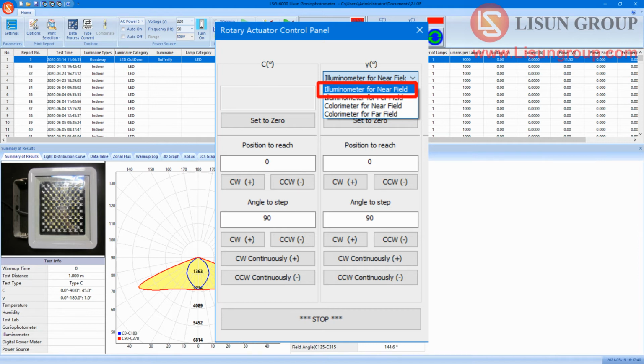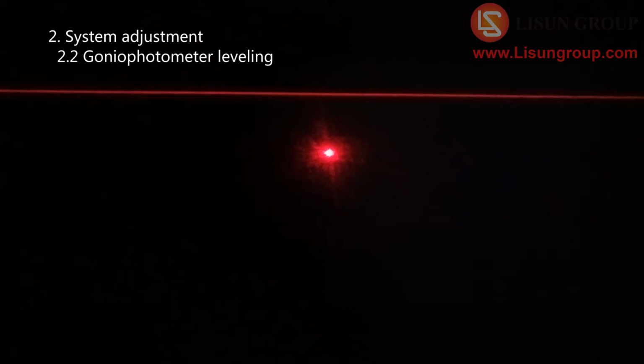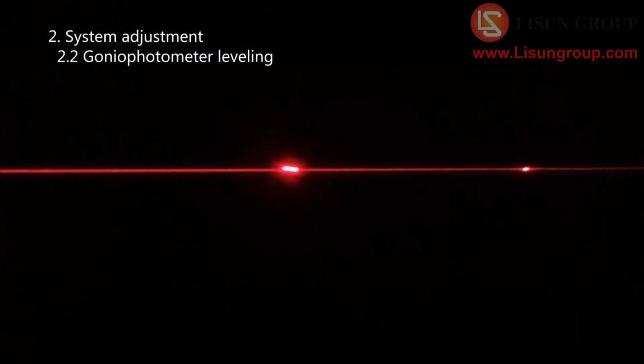Choose Illuminometer for near field. Click this button to make it rotate continuously. Then you can see the laser spot moving on the darkroom wall. Now you need to rotate the screws to adjust the height of the 4 feet of the goniophotometer. Make sure the laser spot and the horizontal laser are completely coincident within the range of 360 degrees.